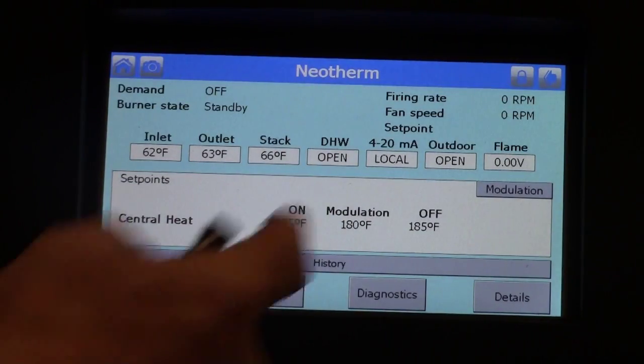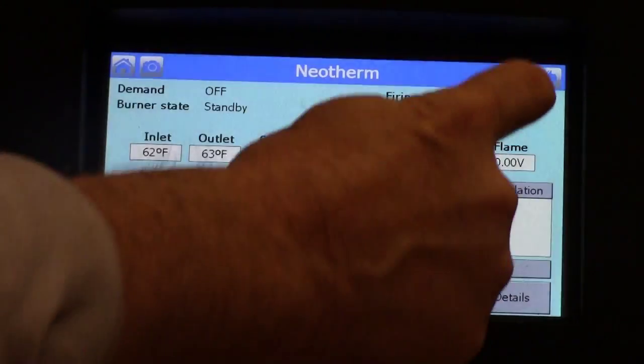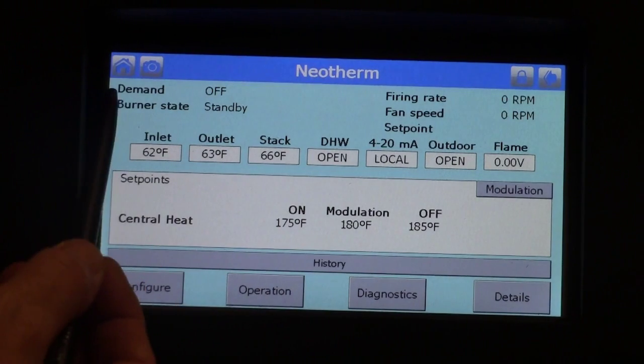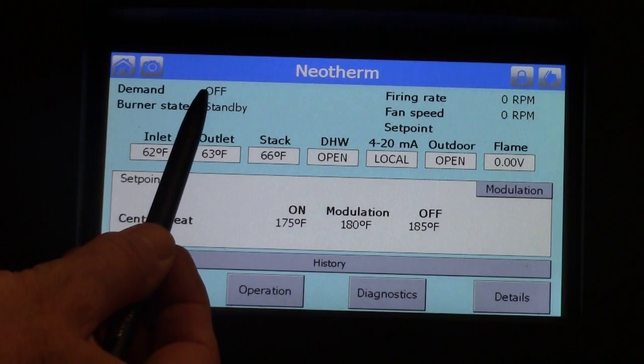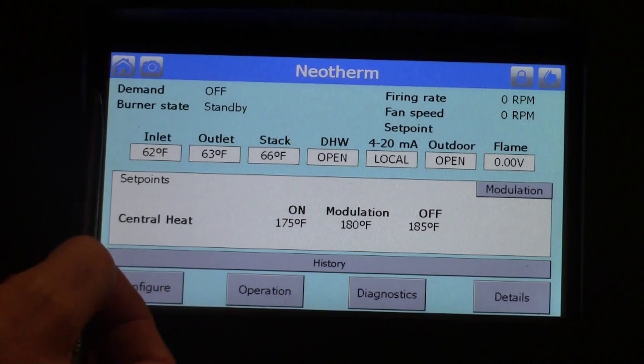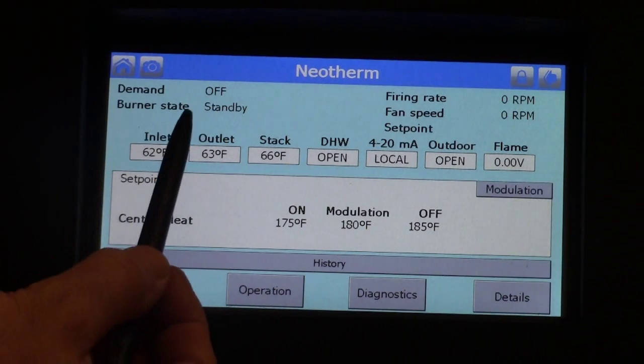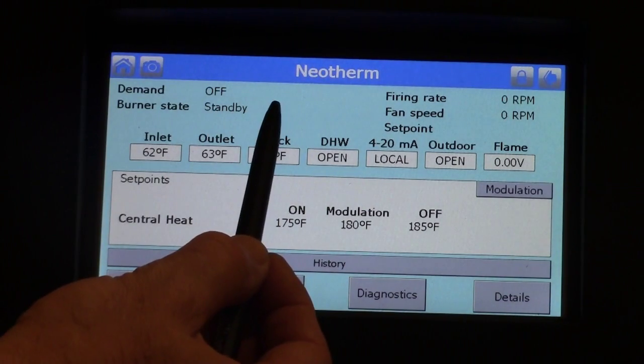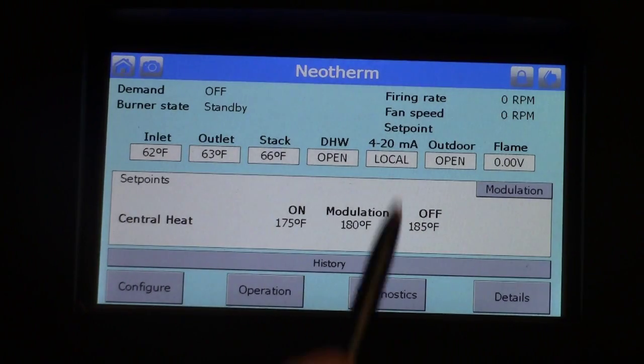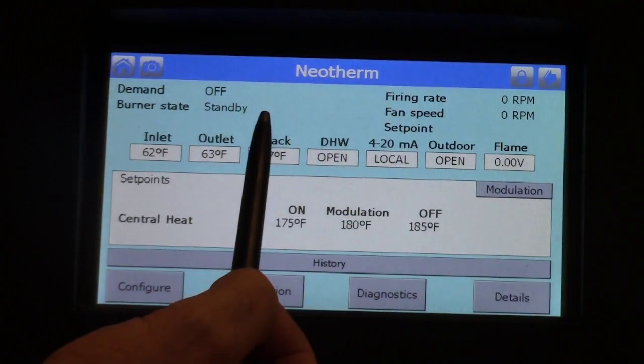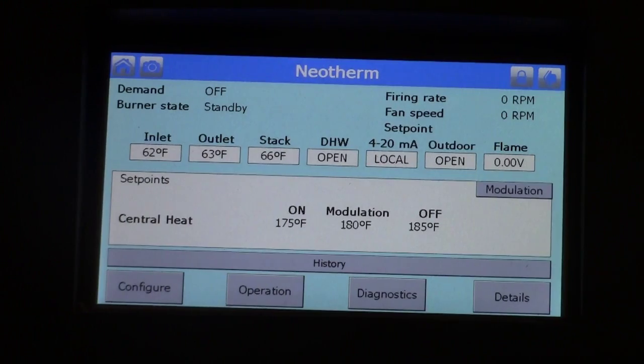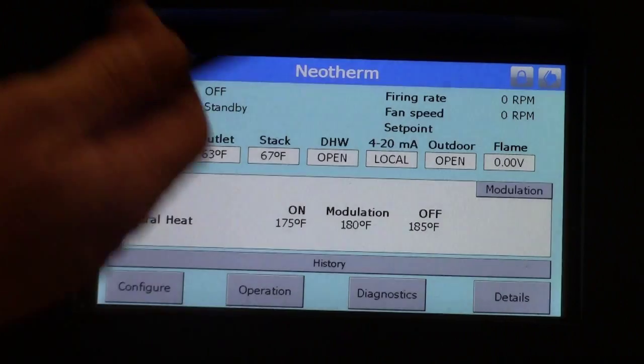Lastly is a back arrow. Hit the back arrow and it will bring us back to the previous screen. Up here is the demand — right now the demand is off, so we do not have a call for heat or hot water. The burner state is in standby. If the burner was running it would read 'run'; if it was driving to pre-purge it would read 'drive to pre-purge,' post-purge, etc. The firing rate is currently at zero RPMs and the fan speed is at zero RPMs, because the boiler demand is off.